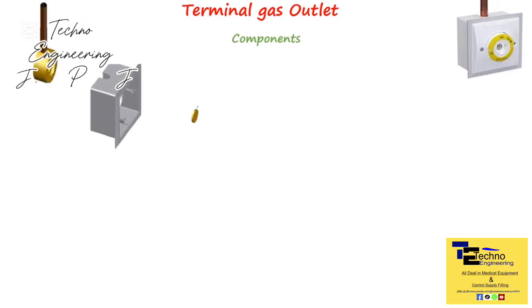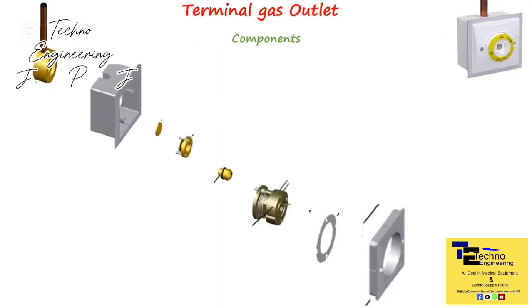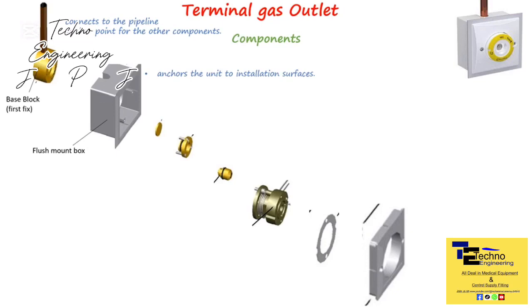These units consist of several essential components. The base block forms the connecting part to the pipeline distribution system, functioning as an anchor point for other elements. Additionally, the flush box secures the terminal unit to various surfaces such as walls or ceilings during installation. The secondary valve, along with its retainer, acts as a backup, providing shut-off functionality and serving as a maintenance valve. It activates when the primary valve is removed for cleaning or servicing purposes.